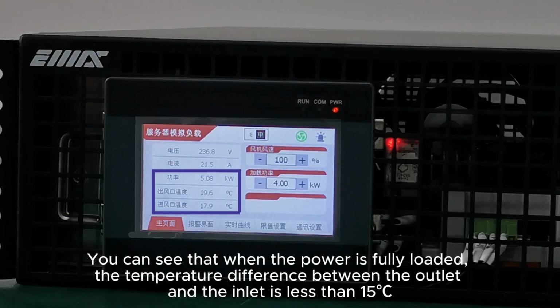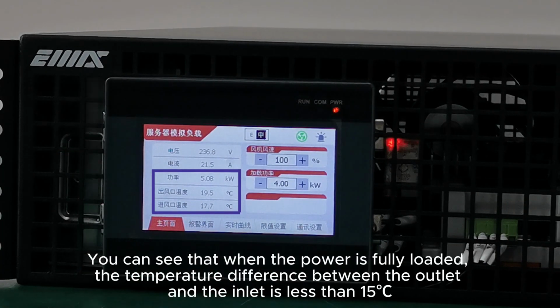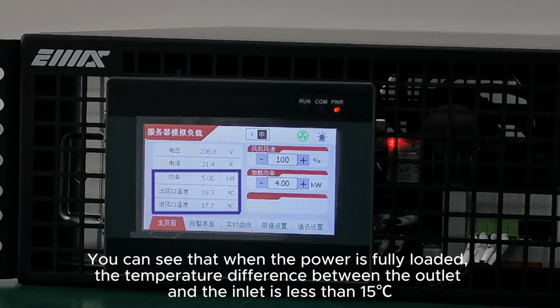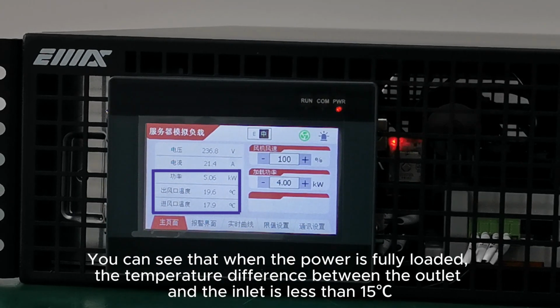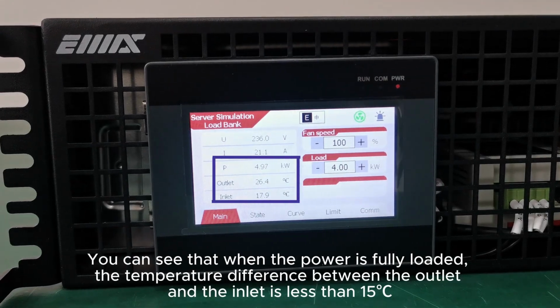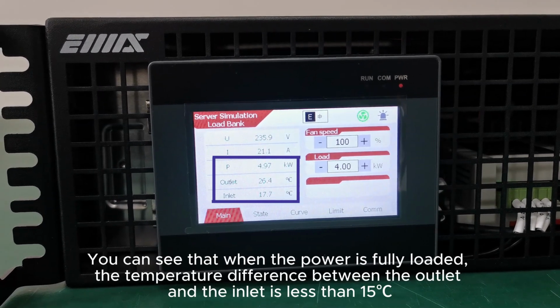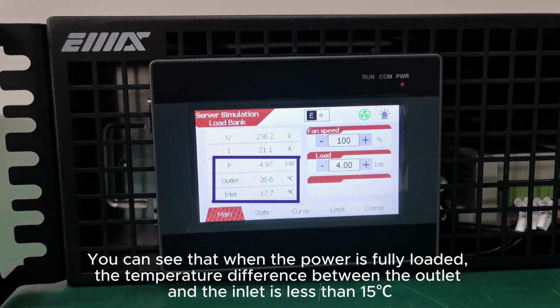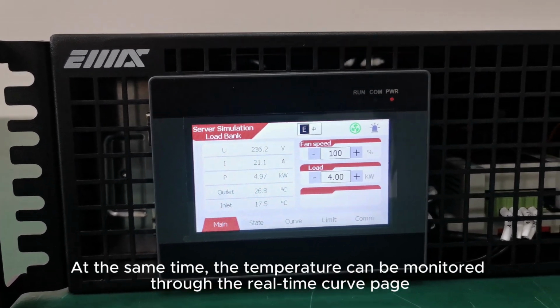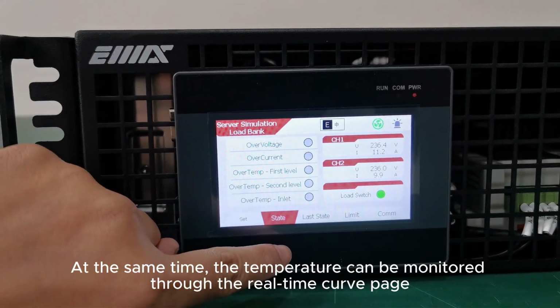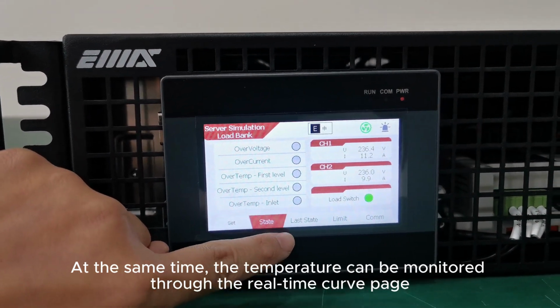You can see that when the power is fully loaded, the temperature difference between the outlet and the inlet is less than 15 degrees centigrade. At the same time, the temperature can be monitored through the real-time curve page.